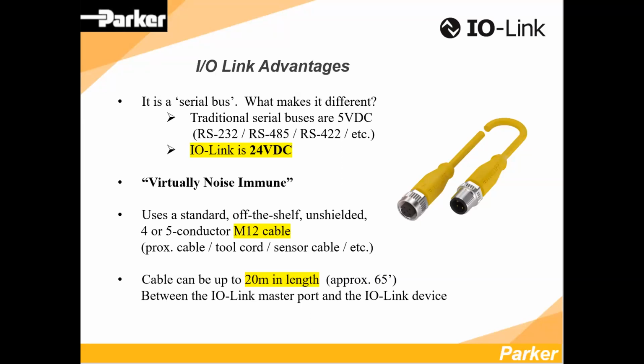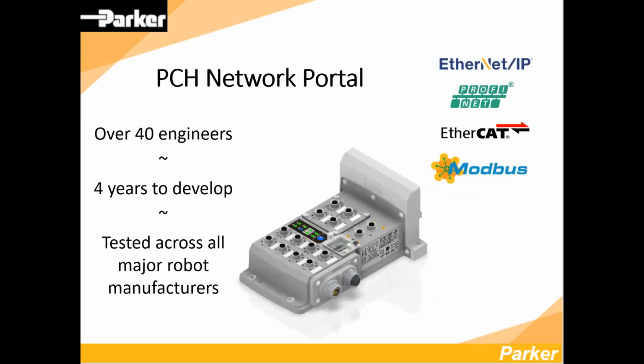It uses an off-the-shelf, basically prox cable, tool cord, sensor cable, whatever you guys call these multi-conductor unshielded M12 cables. By spec, you can go up to 20 meters, approximately 65 feet, between the master port and the sensor itself. So there is a limitation there. Usually that's more than enough to centrally locate a master and distribute from there, but that is a requirement that does have to be met.